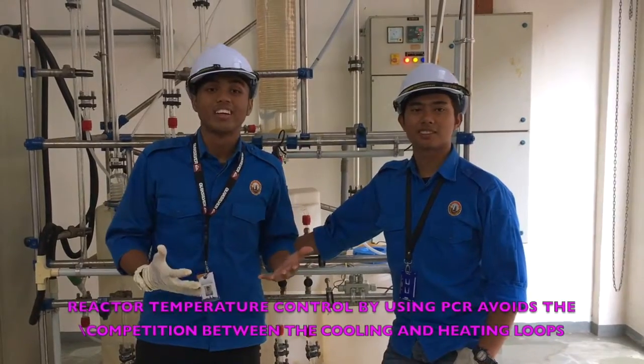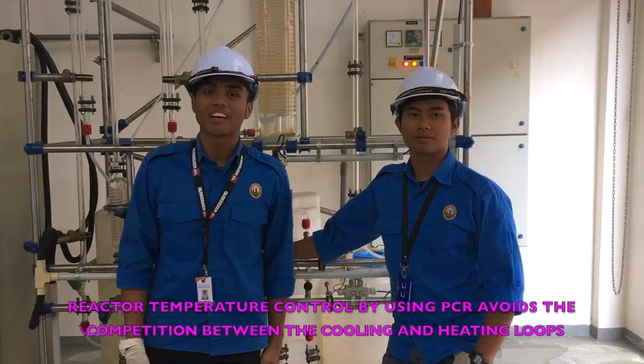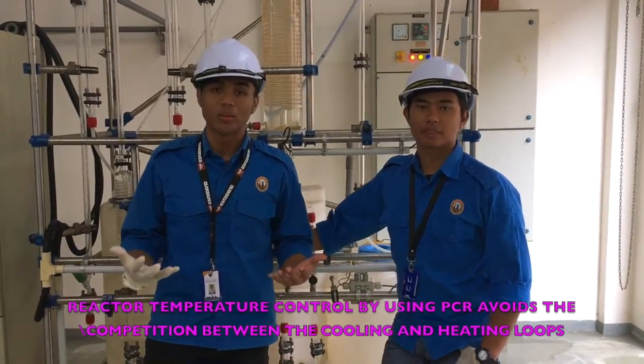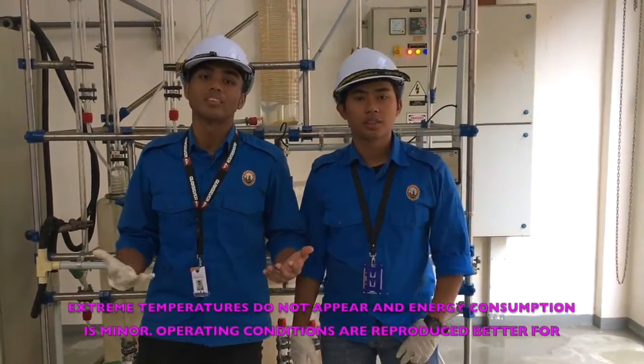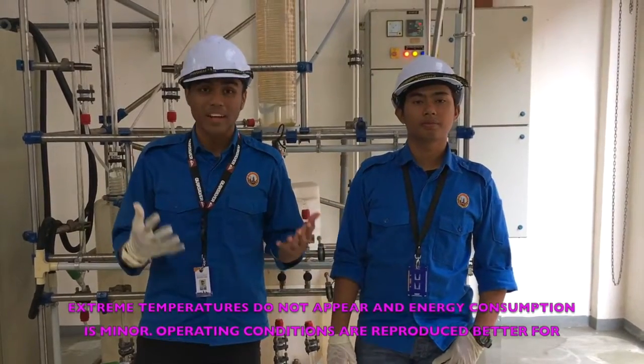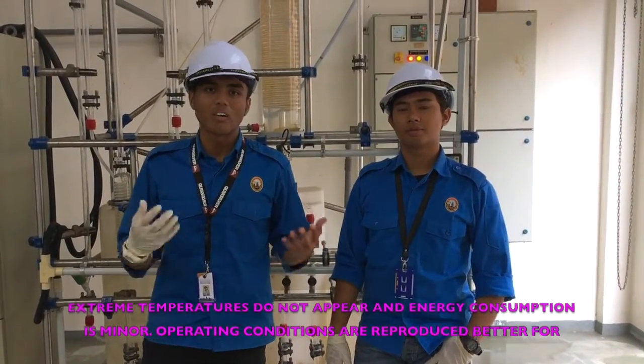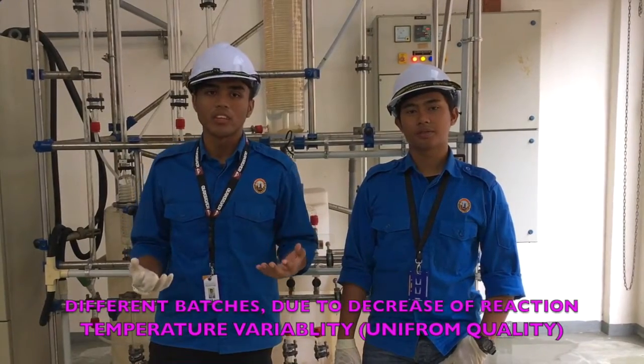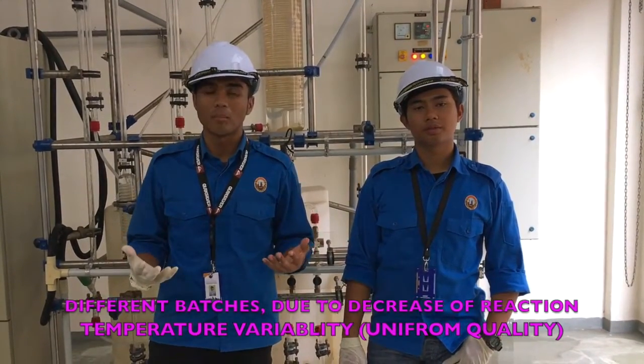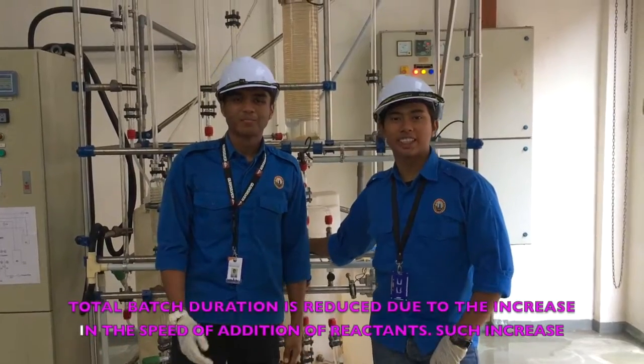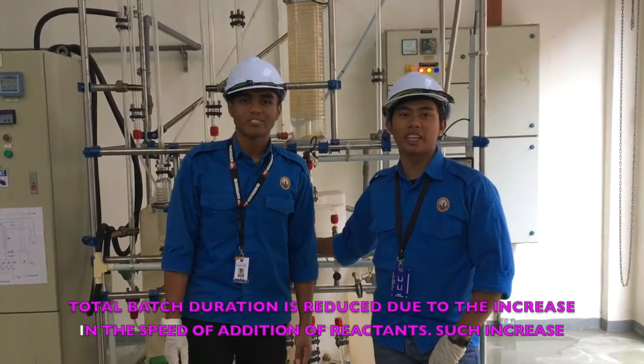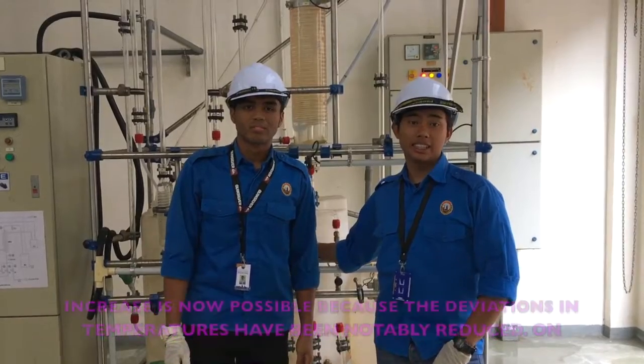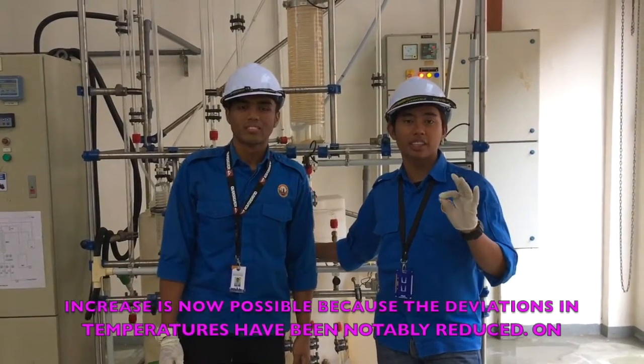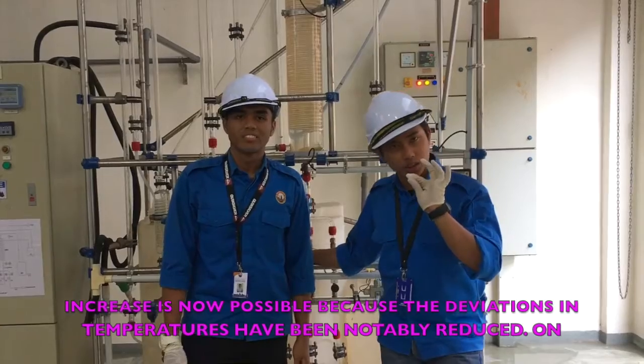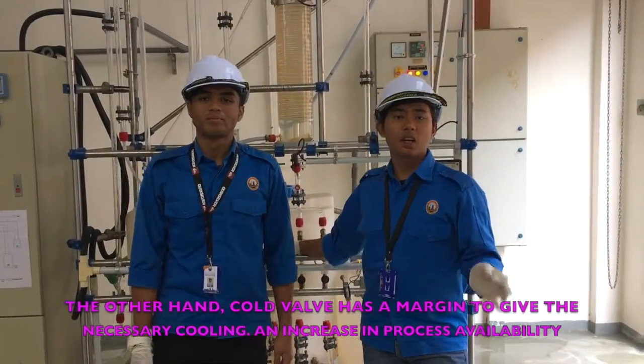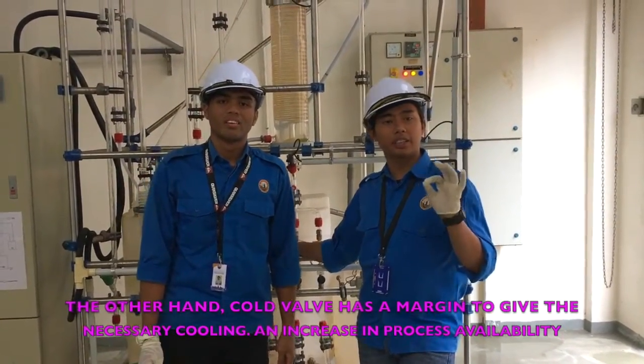Conclusion. In conclusion, reactor temperature control by using PCR avoids the competition between cooling and heating loops. Thus, extreme temperatures do not appear and energy consumption is minor. Operating conditions are reproduced better for the different batches due to decrease of reaction temperature variability. Total batch duration is reduced due to the increase in the speed of addition of reactants. Such an increase is now possible because the deviations in temperatures have been notably reduced. On the other hand, the cold valve has a margin to give the necessary cooling.